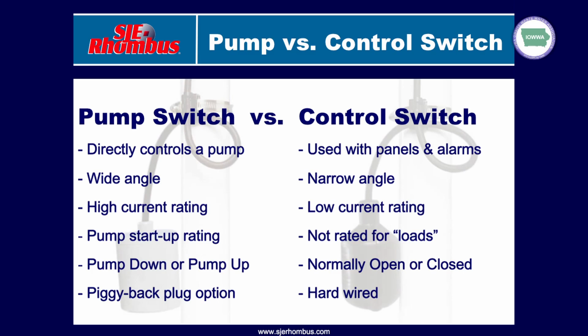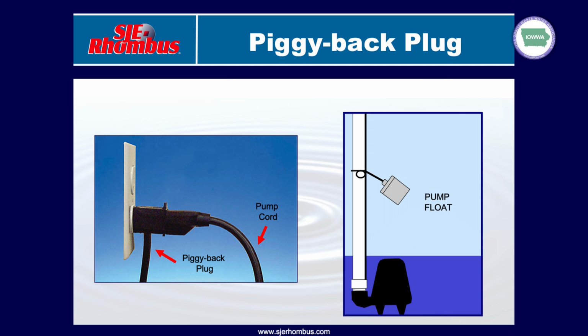Typically with a pump switch, we're going to have a piggyback option. So, and I've got a picture here in just a moment where you're actually going to take the power cord from the pump, plug it right into the switch itself, and then plug that into your power supply. With a control switch, it is always going to be hardwired, whether it's to an alarm or to a control panel. And there's a picture of a piggyback plug where we've got the switch that plugs into our power supply first, and then our pump cord that plugs into the piggyback plug or the switch. Whenever that switch goes to the up position, typically it'll complete the circuit and energize the pump, turn the pump on, switch drops down, shut the pump off.